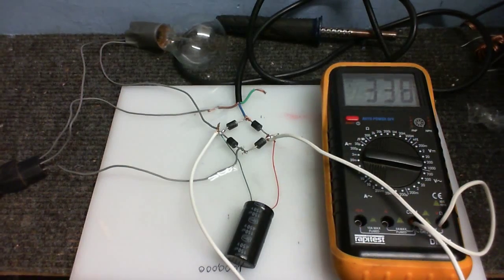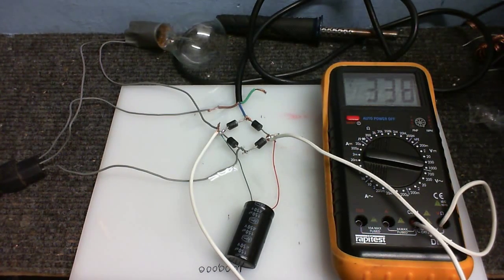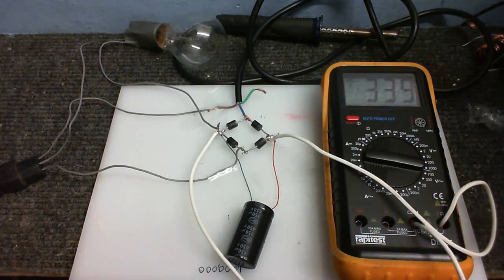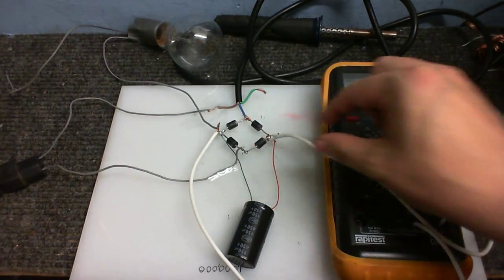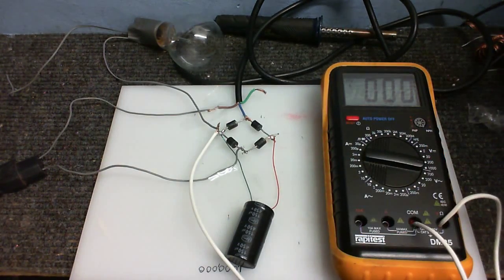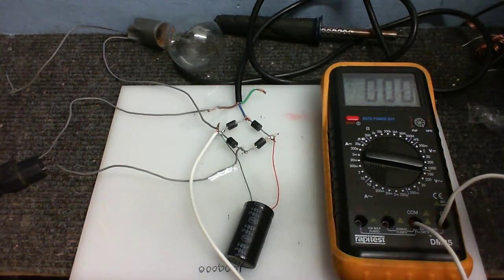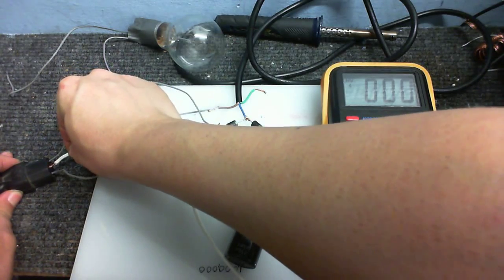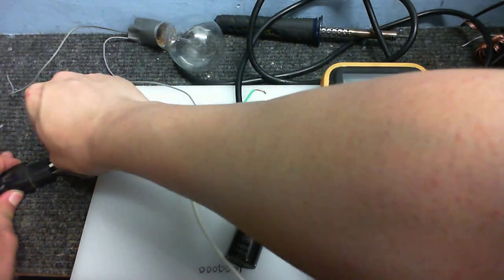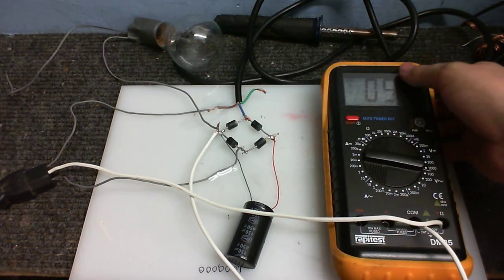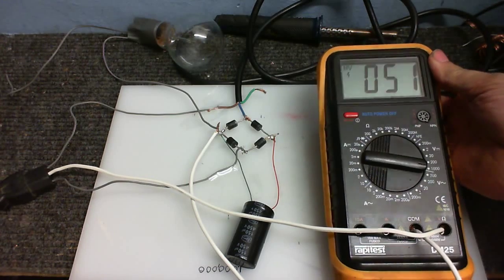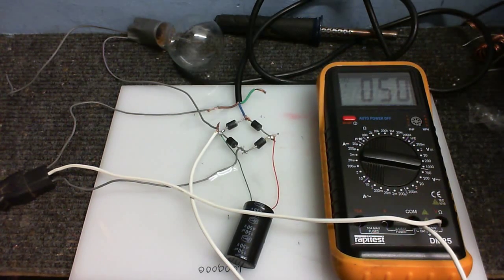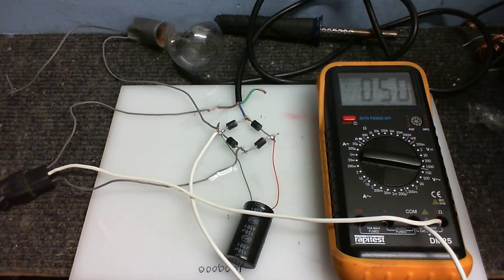And, as you can see, the light bulb does not light up. So that means we've got 0 volts there, right? Well, let's have a look. I'm going to unclick my meter from there. So now I'm going to connect my meter between the 0 volts and the mains earth. And, look at that. We have about 51 volts there. So what is going on?